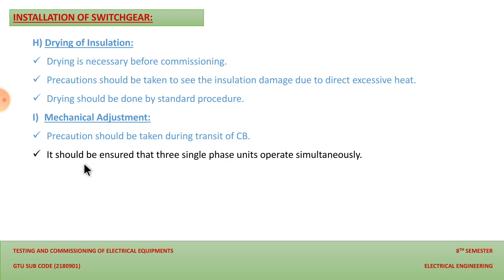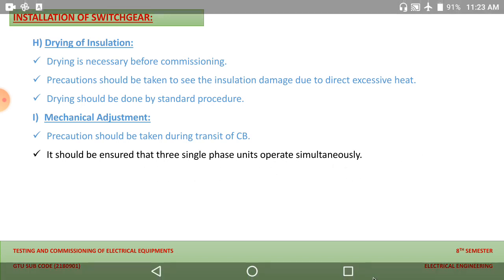The next point is it should be ensured that the three single phase units operate simultaneously. So this is required for the protection purpose. So yes, the connection should be made separately for all three single phase units, and they must be operated simultaneously.